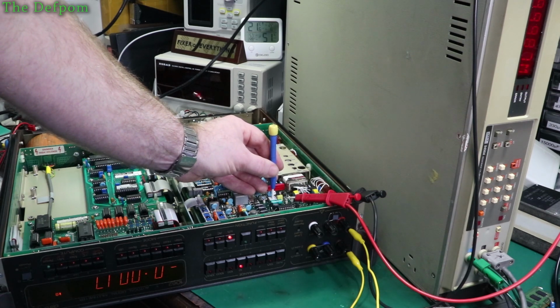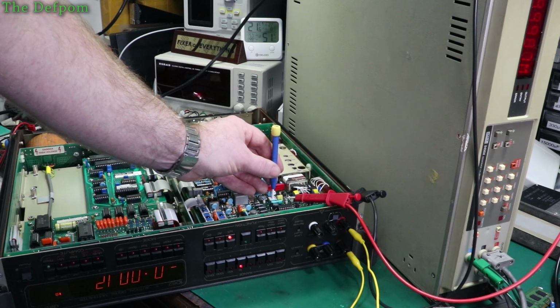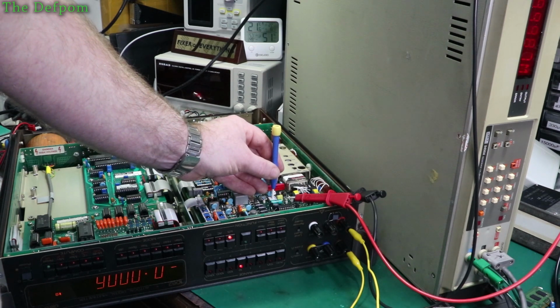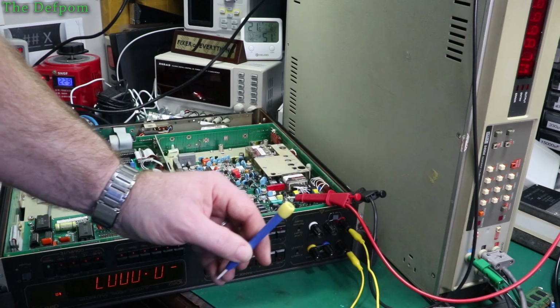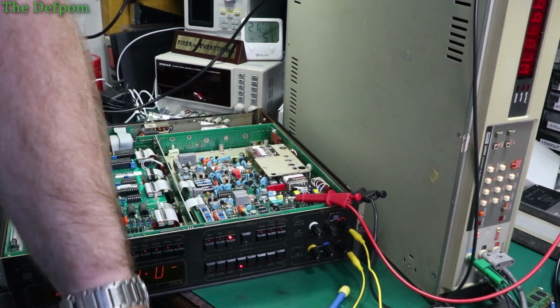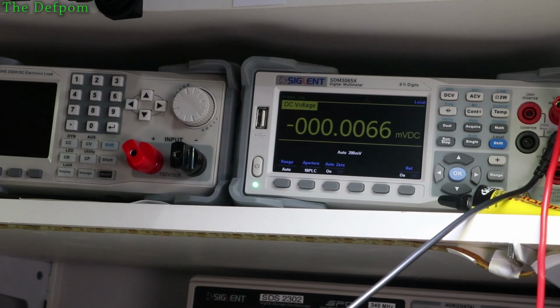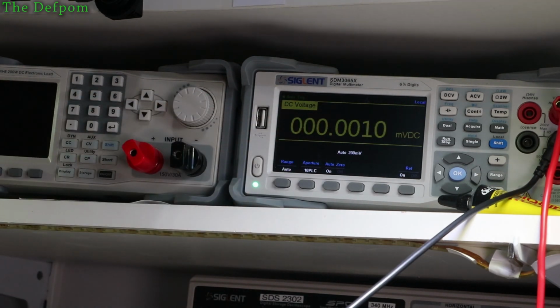It's a bit touchy. It's a shame it's not a 20 turn pot or something on here instead. Those little blue multi-turn pots, or 25 turn or something. Got a little spot here where it's jumping off. I mean, I'm being really fussy here. I'm aiming for perfection, because that's what I tend to do. Right, I think that's about as close as I'm going to get it really. I'll show you. So that's the reading I'm getting. Right, so it should be plus or minus 300 microvolts. So I think I'm within that range. It's got a little bit of drift in there, but you know, noisy environment, that kind of thing. But that's looking pretty good.